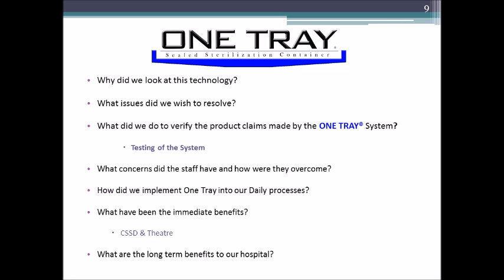But the problem is, in the old model of immediate use with these old container systems, you had a lot of retained moisture left in the sets, which could lead to contamination of the sets or devices. We also wanted to offset costs rather than buying additional spinal or orthopedic sets, so we asked, what if there was a technology that would allow us to better utilize the existing sets we had? That's what the tray allowed us to do.